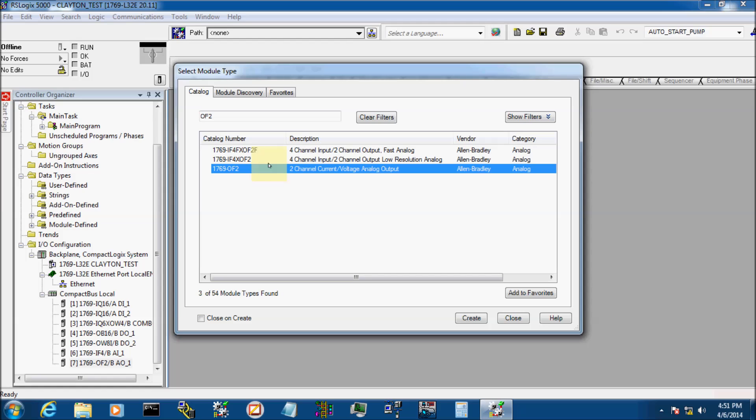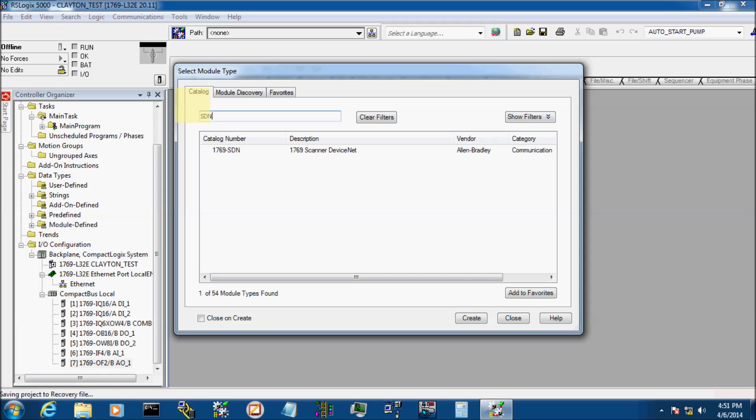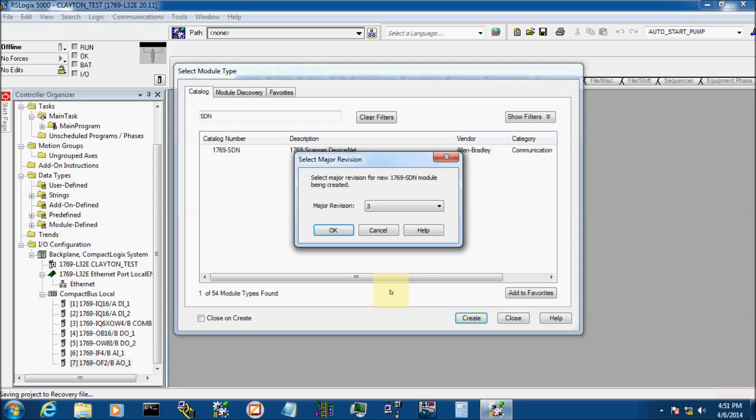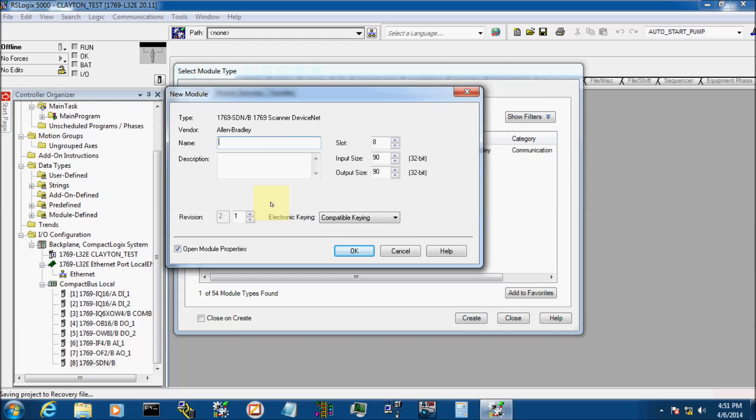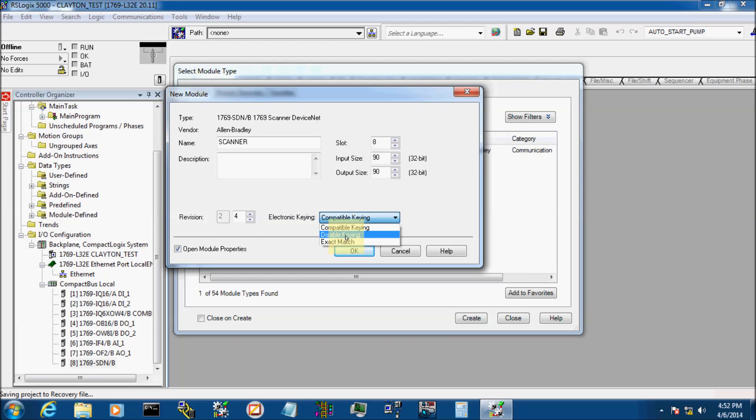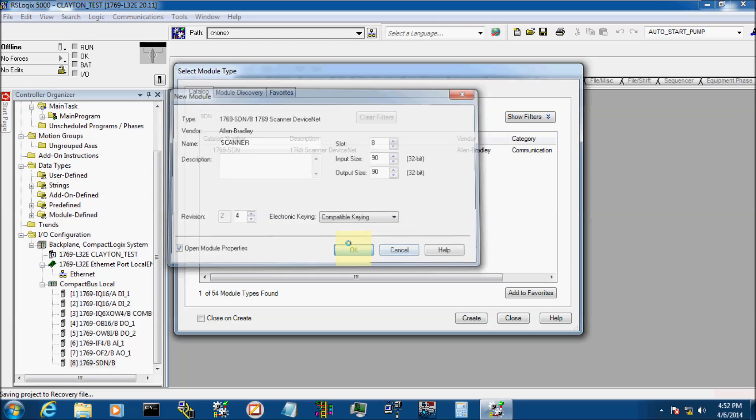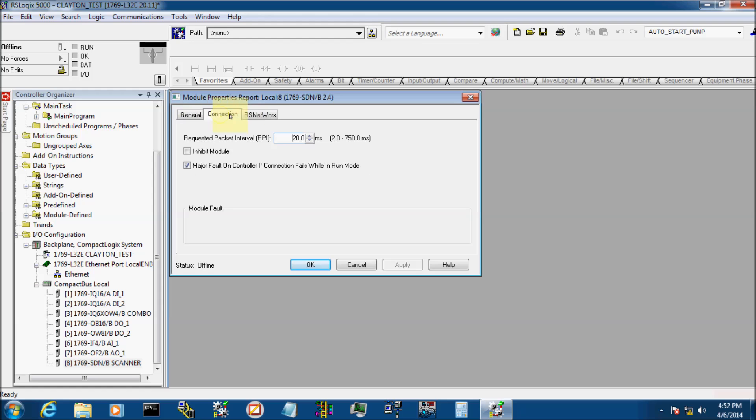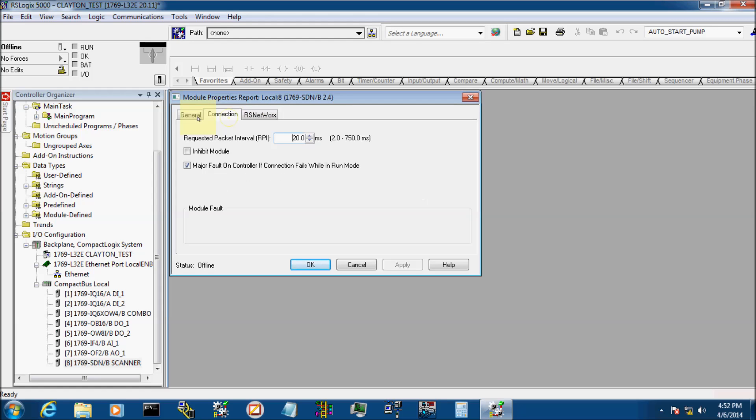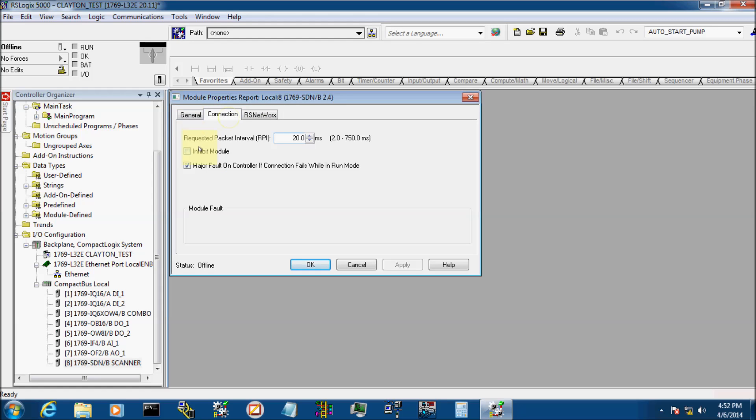And the last card in my rack is actually a scanner card, a DeviceNet scanner card. We're going to go ahead and create that. My major revision on my card is actually 2. We're going to call this scanner. And it's in slot 8, input size 90, output size 90. Mine's actually revision 4, 2.4 down here. We're going to go compatible key. Click OK. It'll pop up with that with my scanner card. It'll pop up another window that lets you configure your RS networks for your scanner card. We're not going to go into that right now. And click OK.